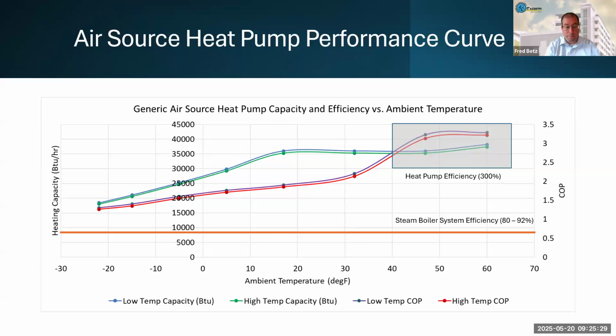So if that's 0 or -10 or -20, the manufacturer of that piece of equipment needs to give you this performance curve, because it has an impact on how much load and what quantity of units you need, and also what the electrical impact is. So if we assumed a COP of 2 or 3 based on these cut sheets, we would be undersizing both our heating capacity and our electrical capacity. So we actually need to go down to 9 and use a COP of about 1.6, 1.8, somewhere in there.